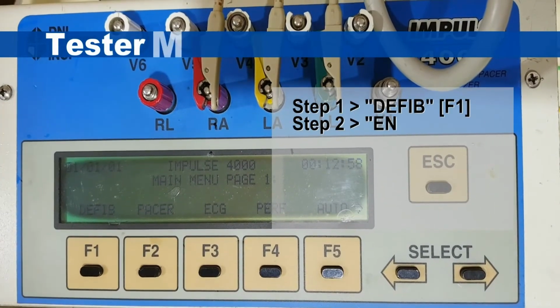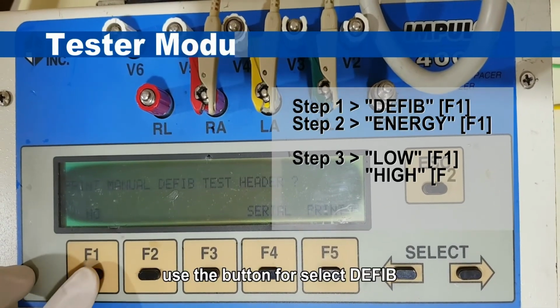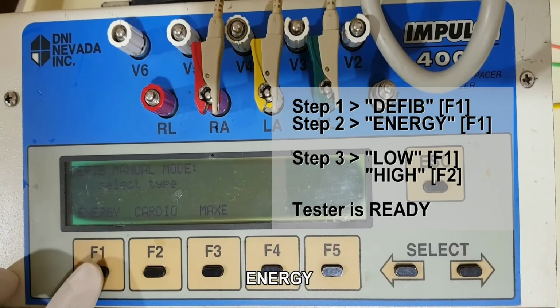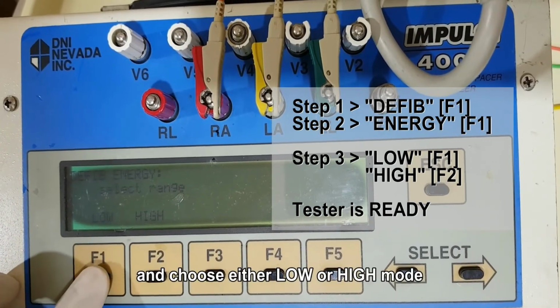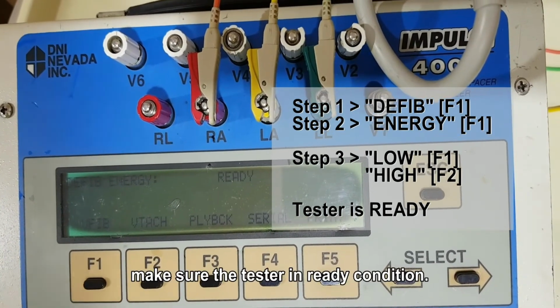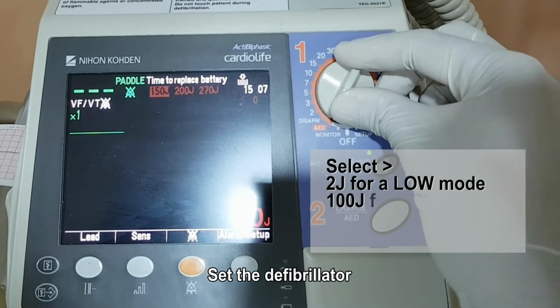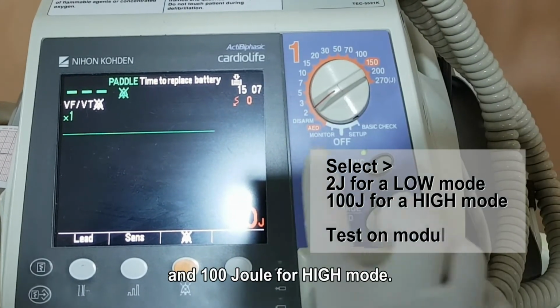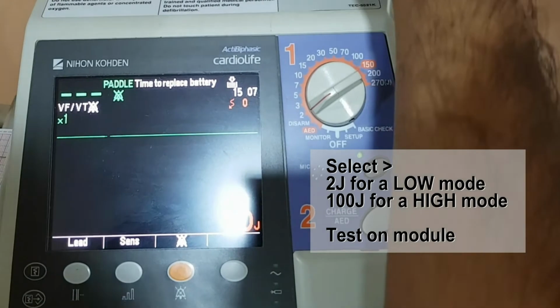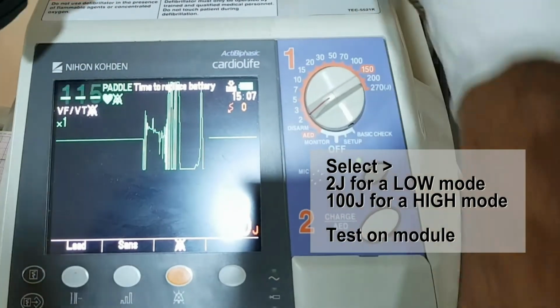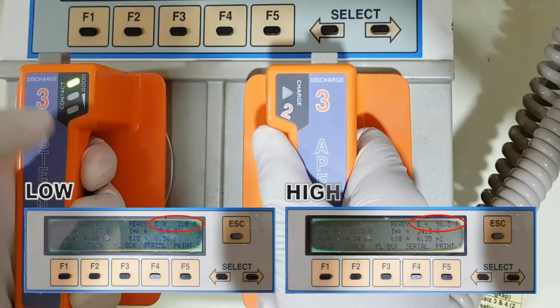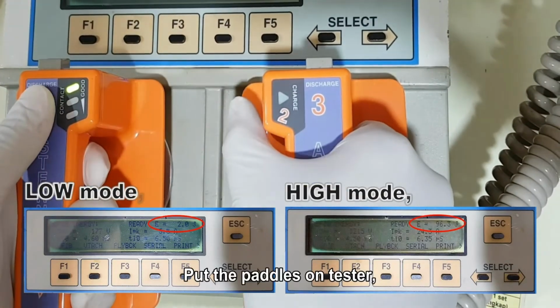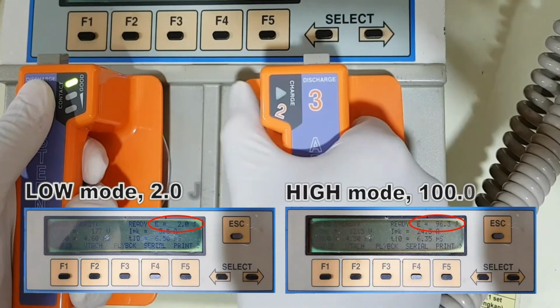For the tester module, use the button for select defib energy and choose either low or high mode. Make sure the tester is in ready condition. Set the defibrillator at 2 Joule for low mode and 100 Joule for high mode. Put the paddles on tester, press charge button and then discharge.